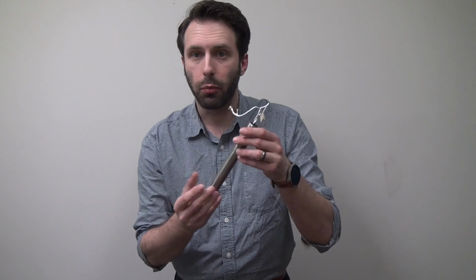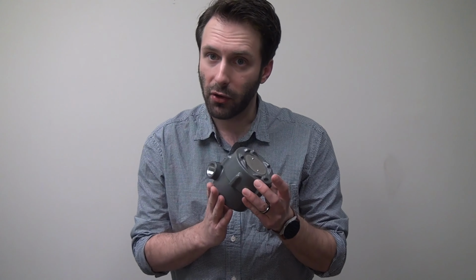In this video, I'm going to show you how to configure a 2700 series ultrasonic level switch with a single point probe. Each 2700 series ultrasonic level switch consists of two parts, the electronics and the probe. Both the electronics and the probe have their own unique model numbers. The electronics will begin with 2700, whereas the probes will start with either 371 or 372.